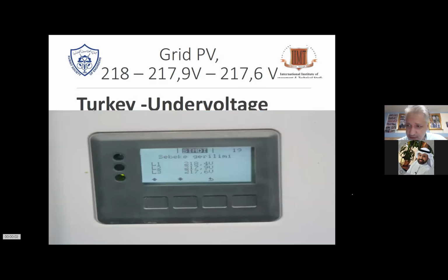This is a system in Turkey, which is actually too low. So there I made the difference. I went up to 230 volt. So I upgraded the tap settings from 20 to 30. That means there's a much stabler supply line. This was a 20 kV medium voltage, and like I said, the transformer or the module voltage inside the factory was actually supplying more power into the system to stabilize the malfunctioning transformer, so to say. So there was lots of extra power, so they had losses of 10% just because of the setting.